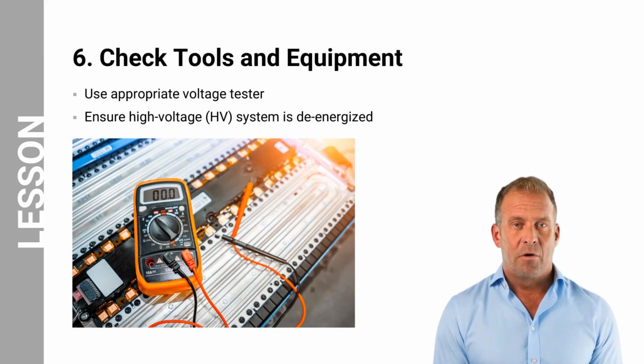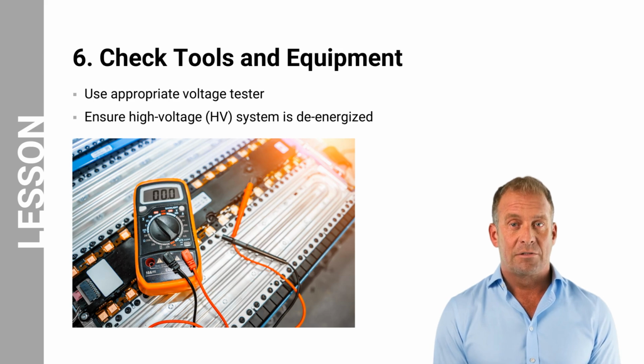Number 6, verify voltage. Voltage verification is a critical safety step to ensure the high-voltage system is de-energized and safe to work on. Choose a voltage tester that is appropriate for the voltage level of the high-voltage system you will be working on. The voltage tester should be rated for the highest voltage you may encounter. Before attempting any work on the high-voltage system, use the voltage tester to confirm that the system is de-energized. This means there should be no electrical potential in the circuits you will be working on. Always follow the manufacturer's guidelines and best practices for voltage testing, and ensure the voltage tester is properly maintained and calibrated for accurate readings.